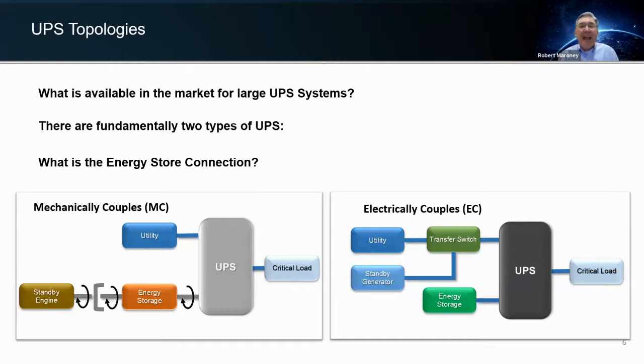One includes mechanically coupled systems, where you have a utility connected to your UPS, and then the UPS's energy storage and backup components are connected physically to the UPS through a diesel genset, usually with a clutch, to an energy storage device into the UPS, thus connected to the critical power. Then you have electrically connected systems, which is more what you see in the United States. About 90% of the UPS in North America is electrically connected.